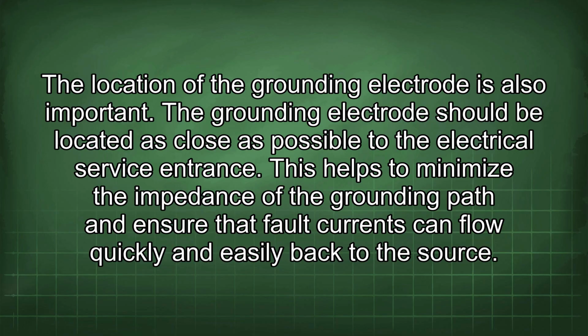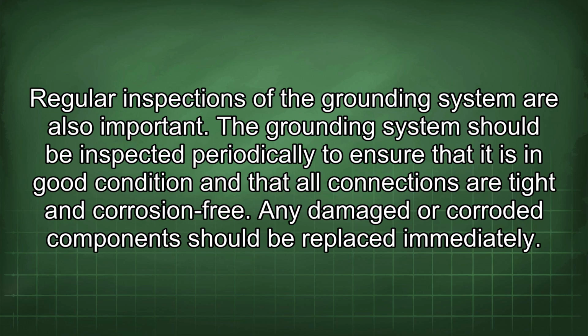The grounding electrode should be located as close as possible to the electrical service entrance. This helps to minimize the impedance of the grounding path and ensure that fault currents can flow quickly and easily back to the source. Regular inspections of the grounding system are also important. The grounding system should be inspected periodically to ensure that it is in good condition and that all connections are tight and corrosion-free. Any damaged or corroded component should be replaced immediately.